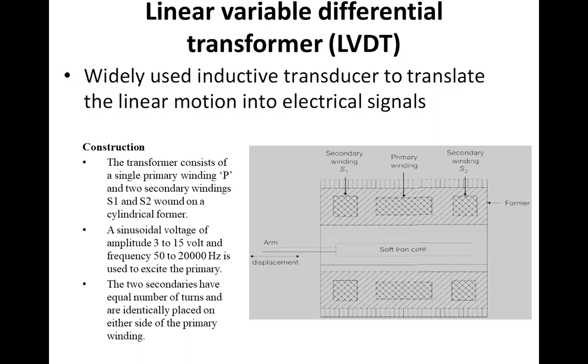Now you can ask, what type of transducer is LVDT? So LVDT is an acronym for Linear Variable Differential Transformer. It is a common type of electromechanical transducer that can convert the rectilinear motion of an object to which it is coupled mechanically into a corresponding electrical signal.